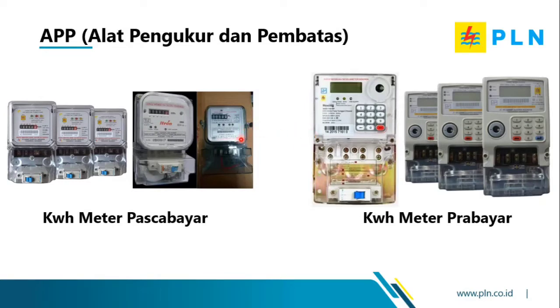Perbedaan secara fisik: pada pasca bayar hanya menampilkan angka stand saja, dan pembatasnya ada di MCB. Sedangkan pada KWH meter prabayar atau listrik prabayar LPB, selain muncul sisa KWH, yang paling utama dapat kita kenali adalah adanya keypad atau tombol angka — angka 1–9, beserta angka 0 dan tombol enter atau OK. Inilah perbedaan mendasar antara keduanya.